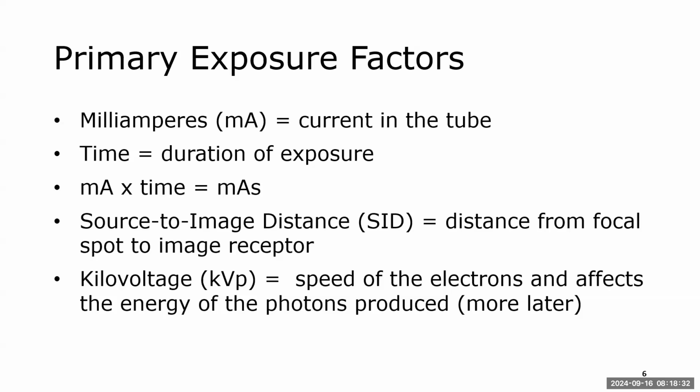Just like in our labs with this Siemens equipment, we don't have the option to break it out and set a separate MA and time. We can set an overall mAs, and then we can adjust the time, remember, in milliseconds, but we can't set the MA. So that's done in the background. And we'll look at the breakdown of that here in just a minute.